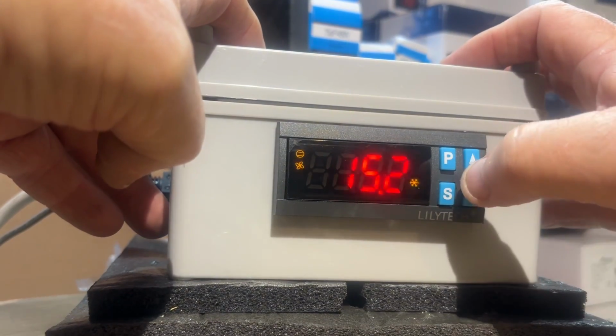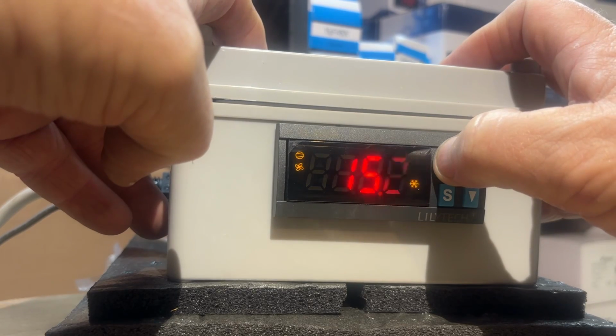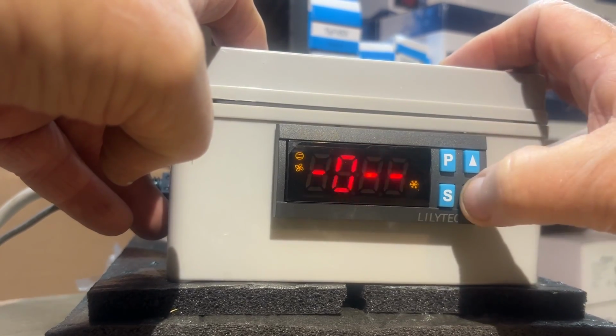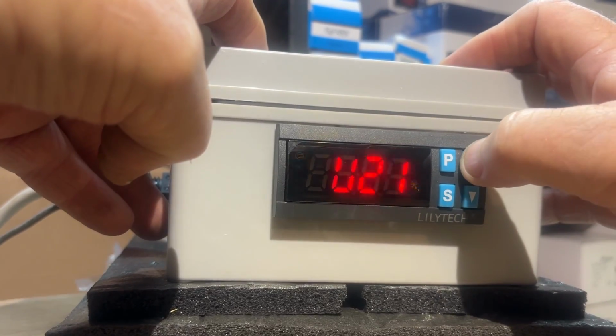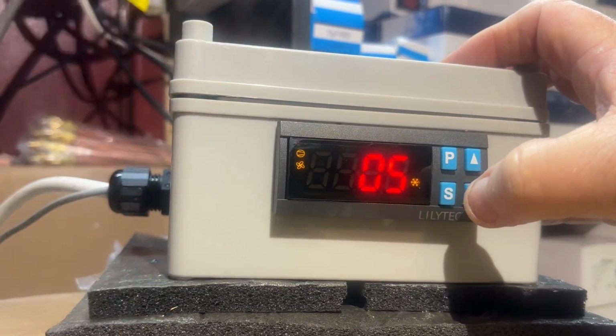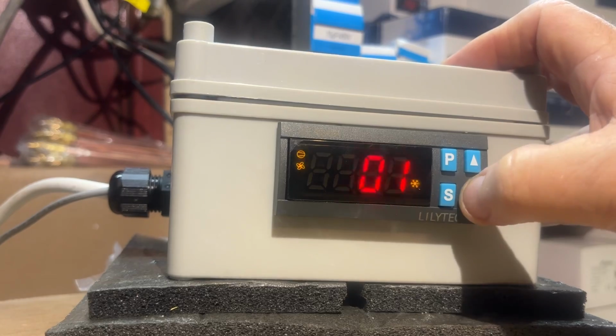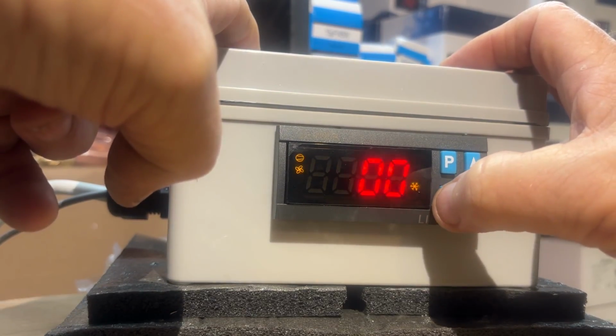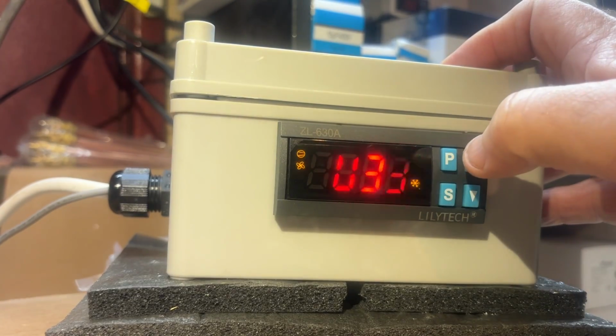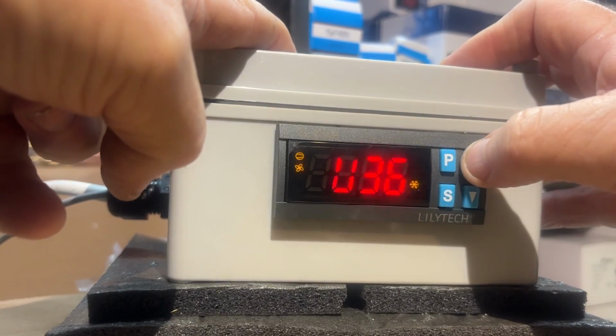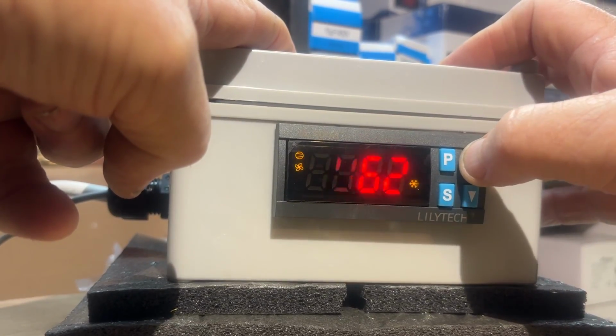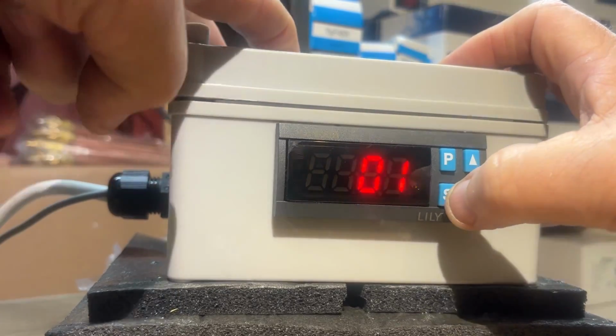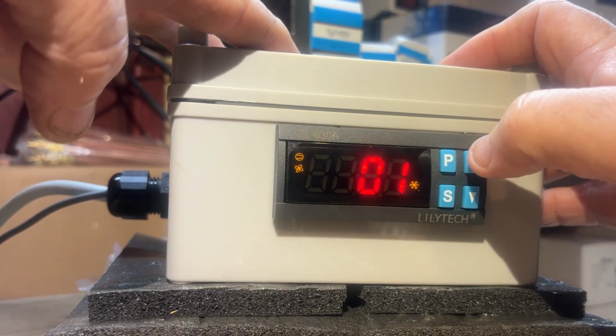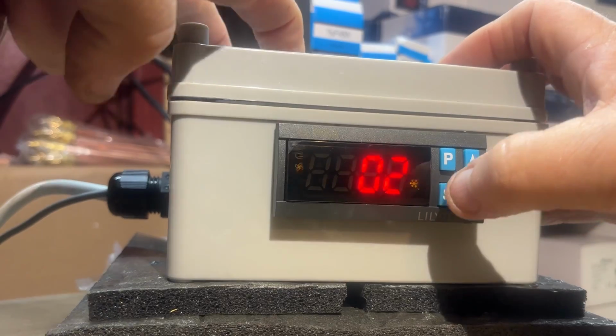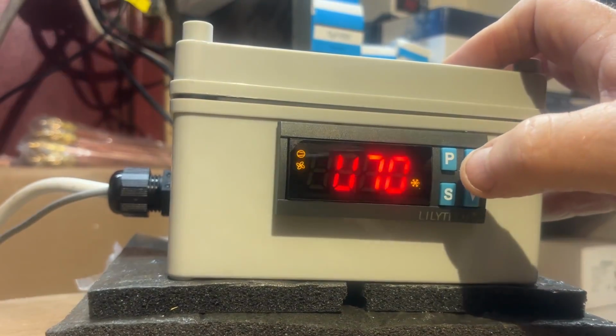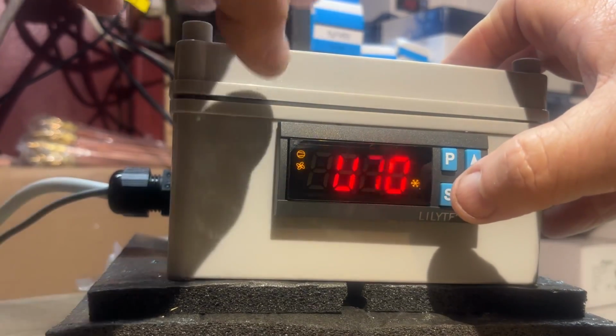Then the next one up is, oh geez, hold on. I've got to go back in. I'll bugger that up. The next one was 33, which is the dripping time. Well, on a fridge, we don't want any dripping time. So take that off. So 33 dripping time, no dripping time. And then the only other one we need to worry about on a fridge is I like to get up to 70, and I like to set 70 to 2, which means when it goes on the defrost, it'll just show the cabinet temperature, so the customer doesn't worry.